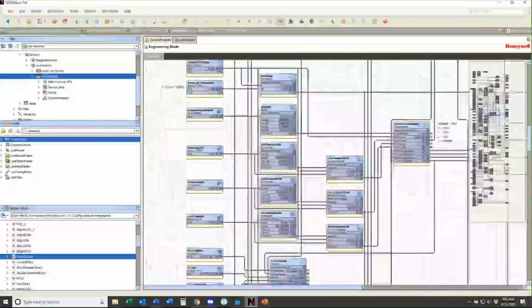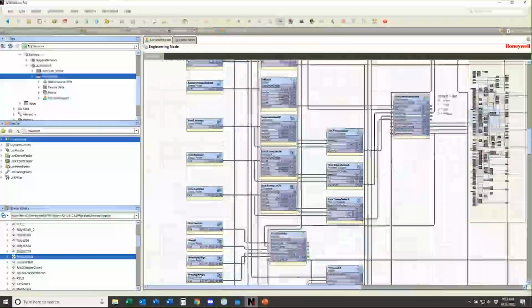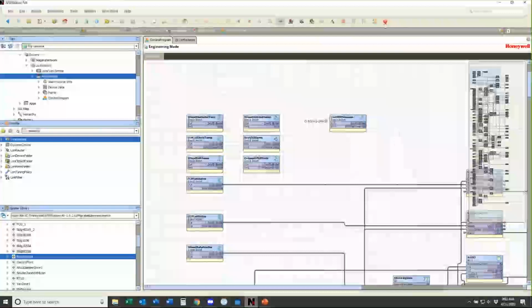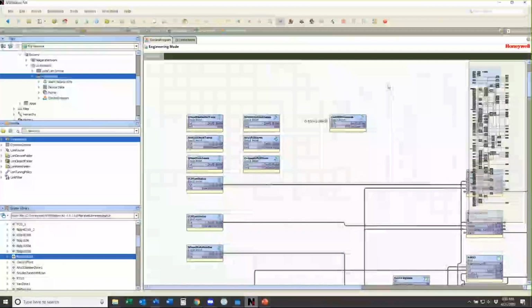What's happening now is the station we created on this wire sheet is being transferred from our Niagara network and Niagara station into the Spyder. Worth talking about while we're waiting - you'll see our red light up here is on because we're in download, so it's telling us we really can't do much right now. Worth talking about is that when we have our wire sheet information, the area where we create our program, that's really an environment for us as a user - that's not what's going into the Spyder, obviously. It's a bunch of ones and zeros or some sort of machine language.